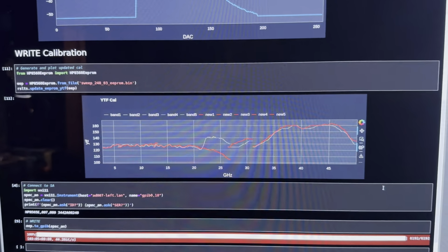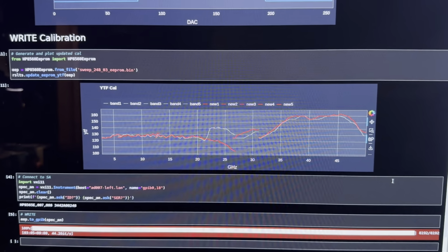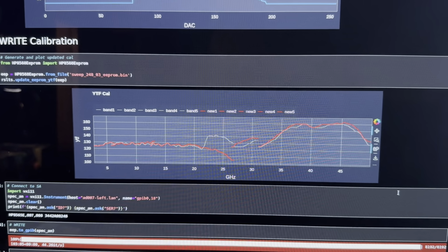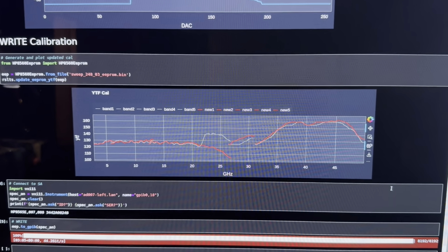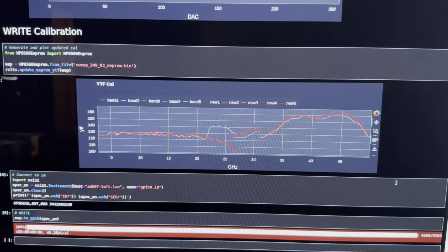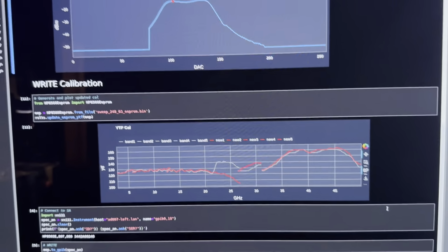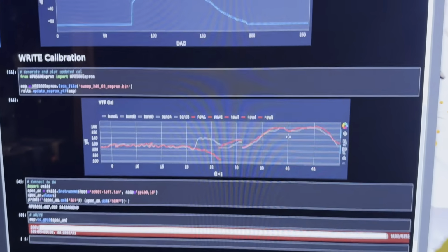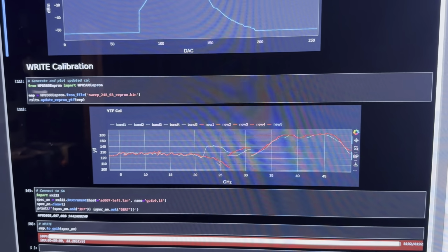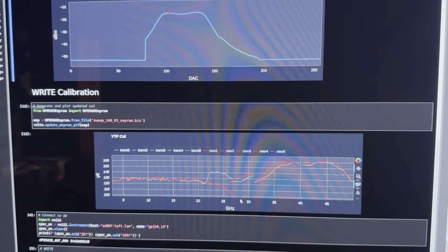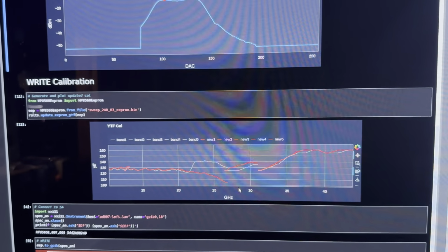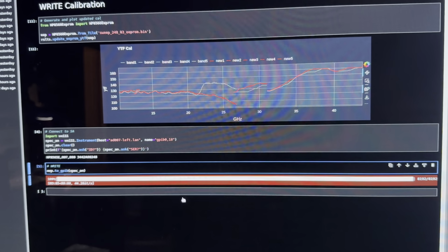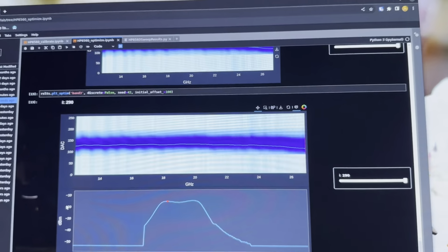And then the result is this, whereas previously in gray, the old calibration had that jump in band 3, where it switched from one hump of the camel to the other hump of the camel, one bandpass portion to the other bandpass portion. Here we stick with one hump through the entire range of the band, and we expect that to have much better dynamic range. And so we would write that out to GPIB and recalibrate, except actually I have already done that.